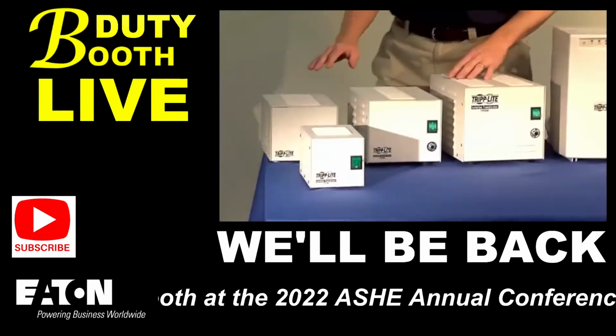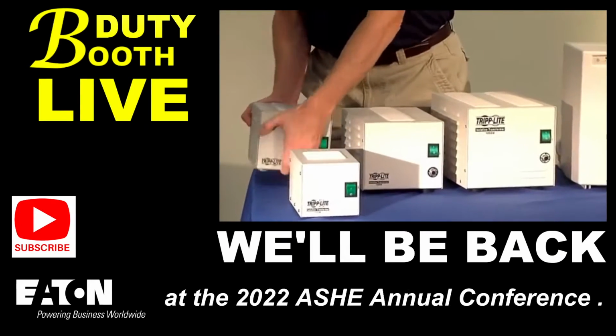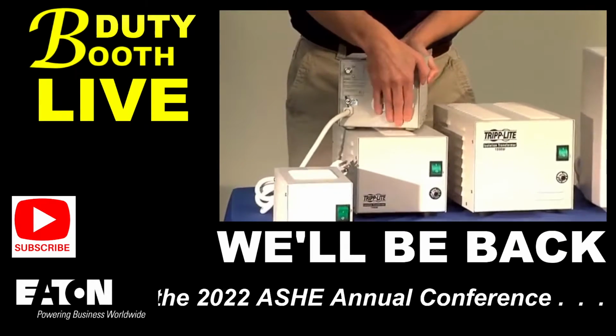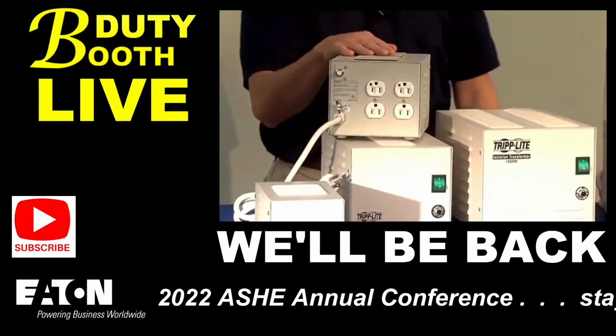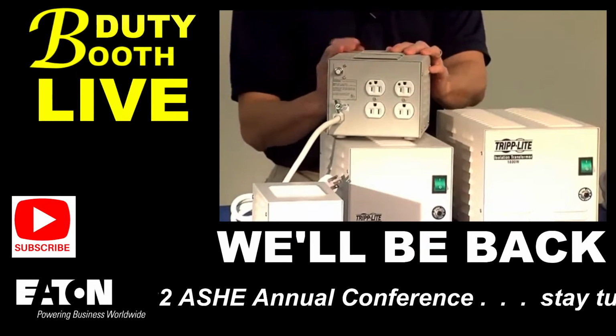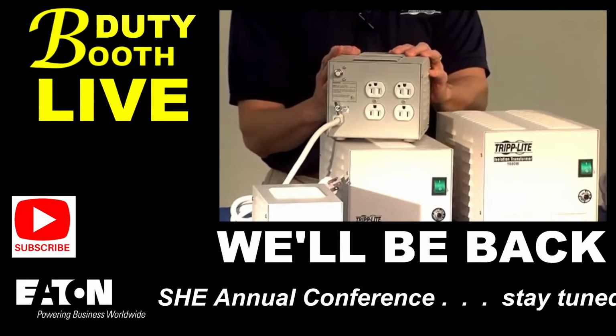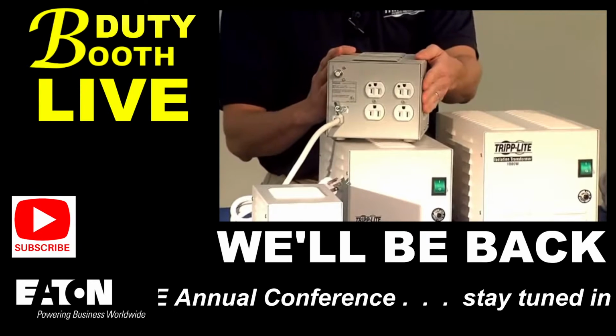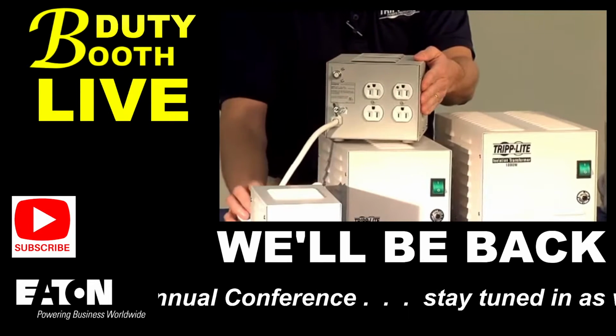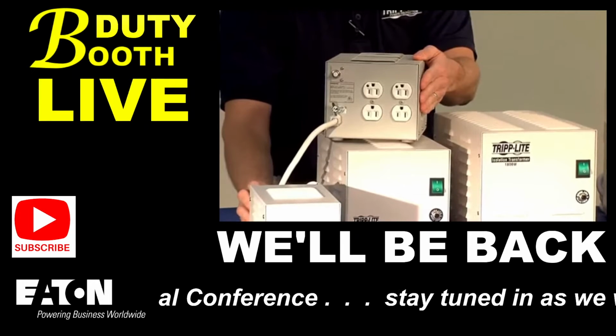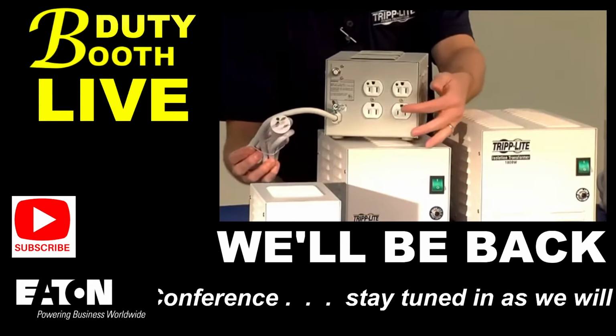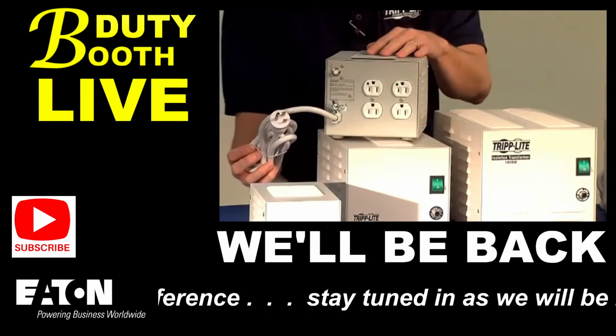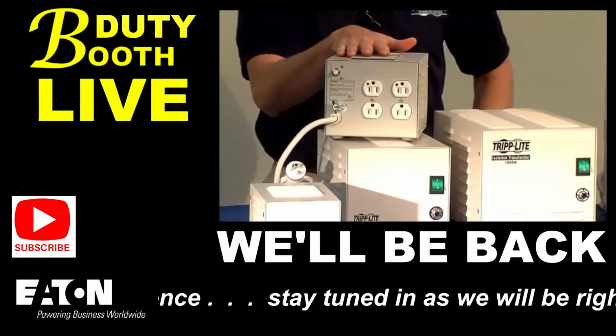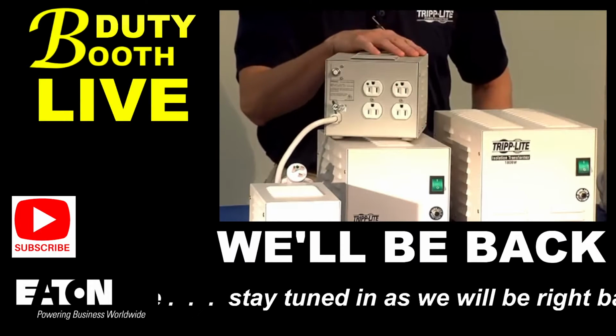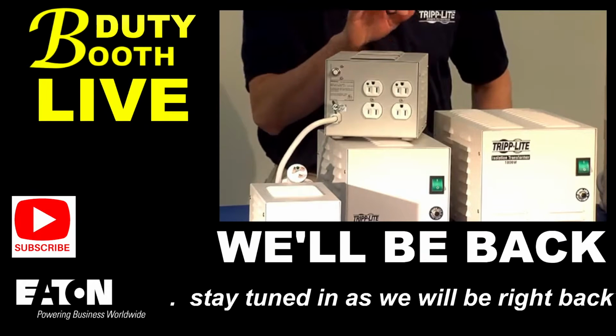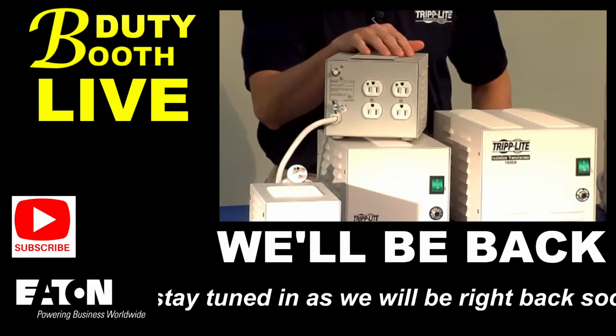If downtime is not a concern, sell them a Tripp Lite medical-grade isolation transformer. It includes many of the same features as a UPS, but not battery backup—built-in isolation transformer, surge suppression, line noise filtering, and hospital-grade outlets and plugs. Customers use these products not only to maintain compliance, but to clean or condition their power as well.